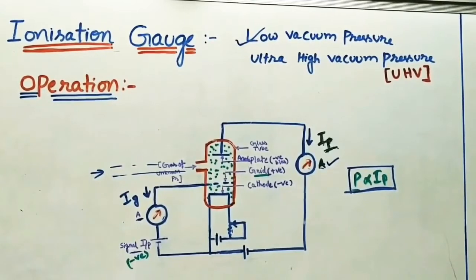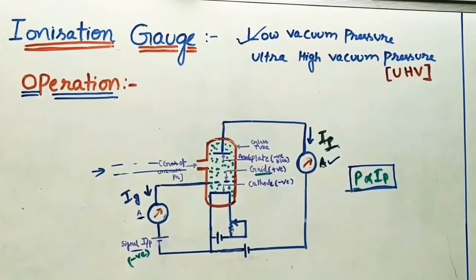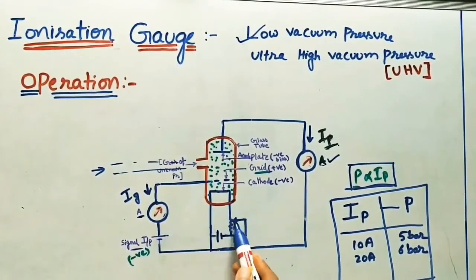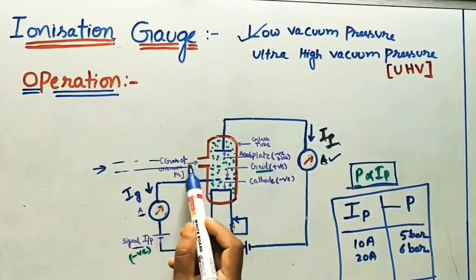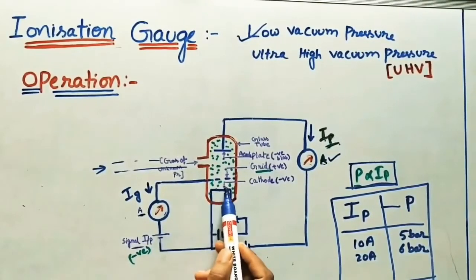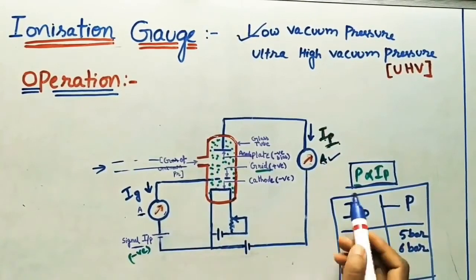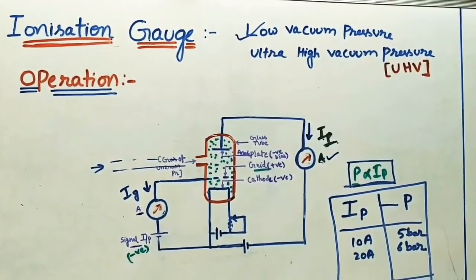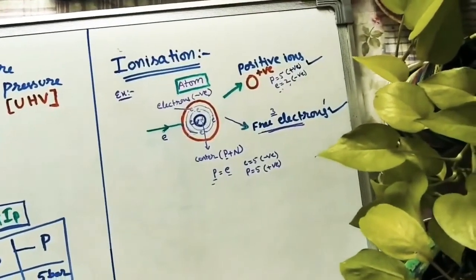The limitations are: the filament will burn frequently, because we are heating it at high temperatures by giving different currents. Also, because we are sending gas into it, the gas will decompose due to the filament temperature — that is the main disadvantage. Additionally, for different gases, we have to prepare different calibrated scales, which is also a disadvantage of this gauge. If you like this video, please subscribe to my channel and share with your friends. Thank you for watching.